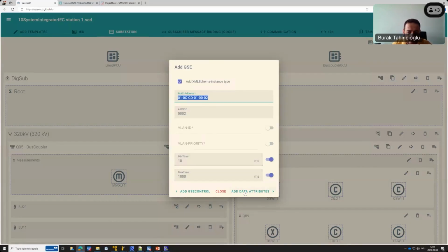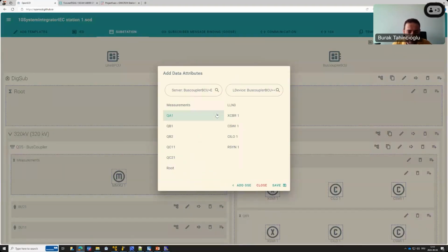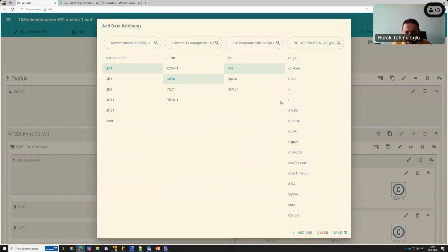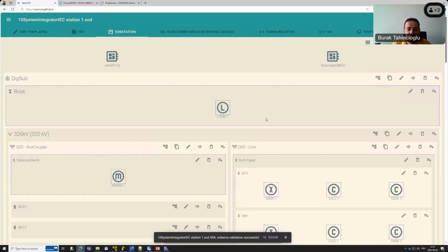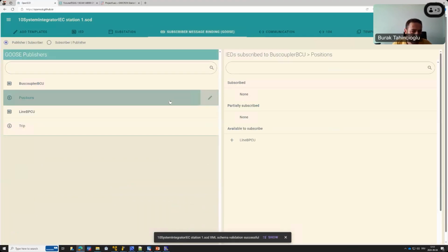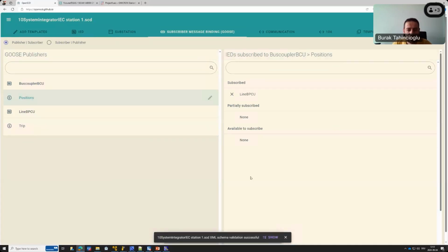It's important to have descriptive control block parameters and communication parameters, because they are in the header of the GOOSE, not in the content. Moving on with adding some data attributes, I will not do all, but just show how to add one position information with status and quality, and say save. And please imagine I have added all of this. Next would be subscribing to these positions with the line bay controller. That will also be two steps to accomplish this task.